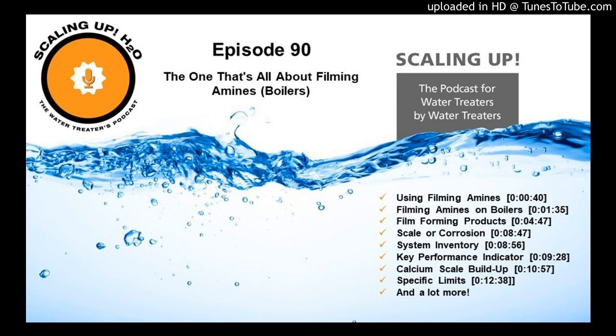So let me ask this. Ideally, we want it going into the feed water line close to the boiler, so it sees that first, or going directly into the boiler if we can do that through a manifold. If we can't do that, and let's say we can't, so now we're feeding into a feed water tank, and then ideally we're metering off of the makeup, so we have a metered amount of filming amine product that's going into the system. Let's say we don't have a water meter. How do we feed it then, or is that not the right product then?